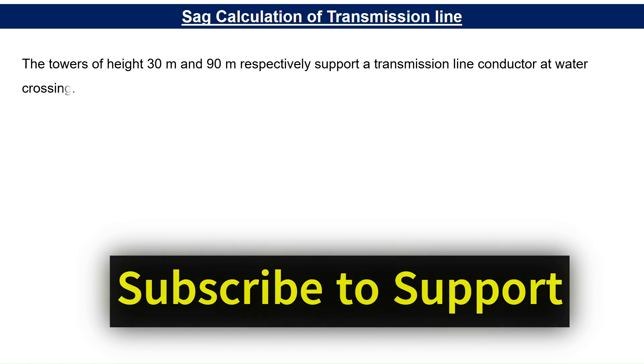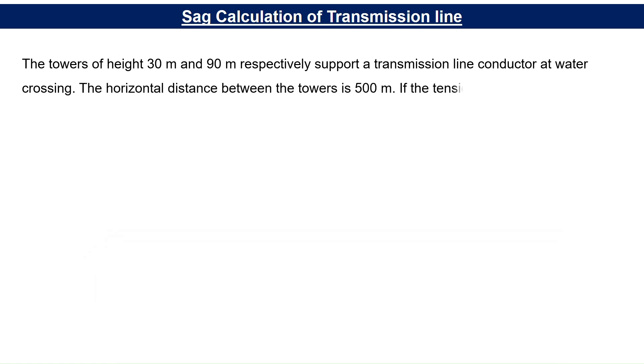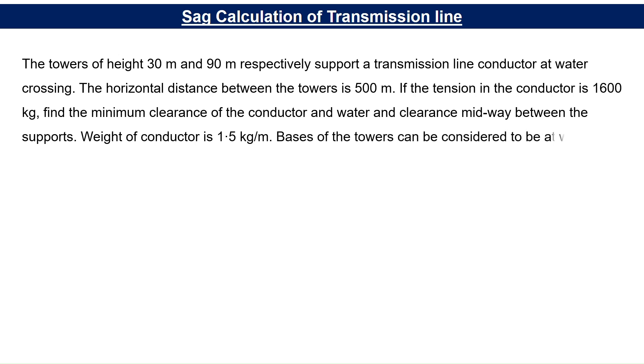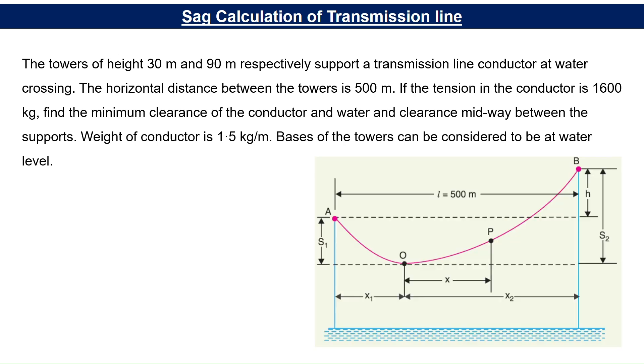The example is: two towers of height 30 meters and 90 meters respectively support a transmission line conductor over water. The horizontal distance between the towers is 500 meters. If the tension in the conductor is 1600 kg, find the minimum clearance of the conductor above water and the clearance midway between the supports. The weight of the conductor is 1.5 kg per meter. The base of the towers can be considered to be at water level.